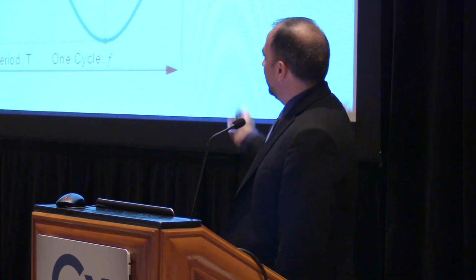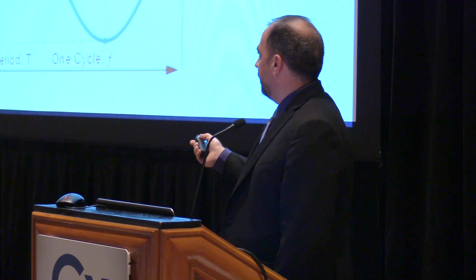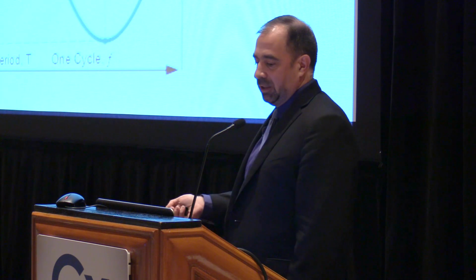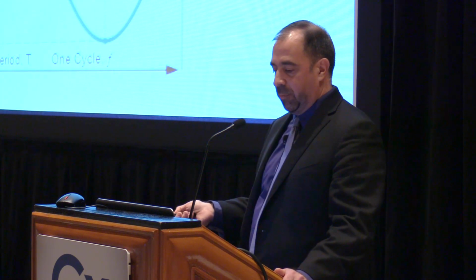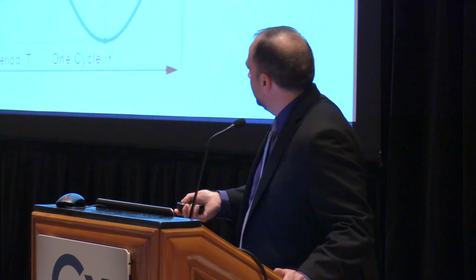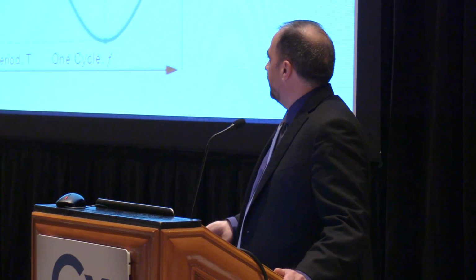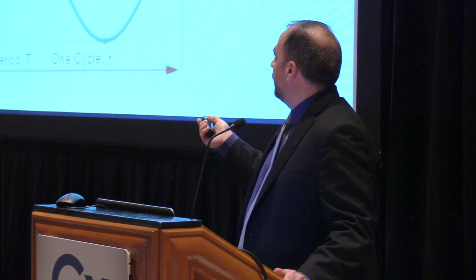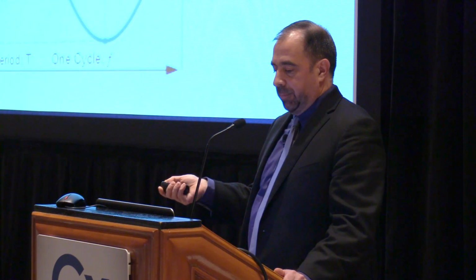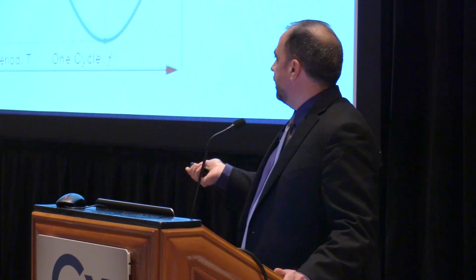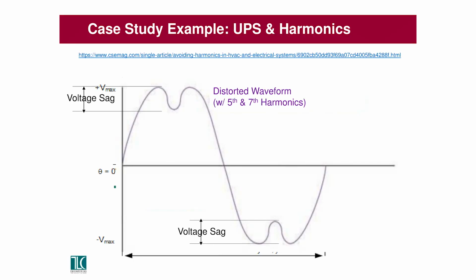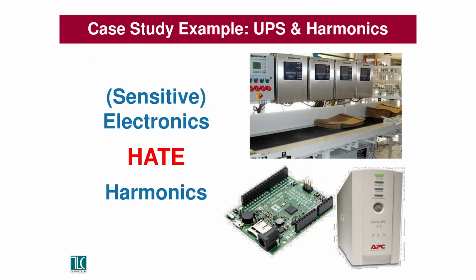If you remember from your high school physics class, this is what a typical voltage sine wave should look like, nice and clean. It doesn't really look like that in reality, but when we have big harmonic distortion, you get all these little waves in between. This happens to be representing the 5th and 7th harmonics that's going on with those chiller VFDs, and the resultant curve looks something like that, and those nasty little dips in there really cause havoc on sensitive electronics, different controllers.